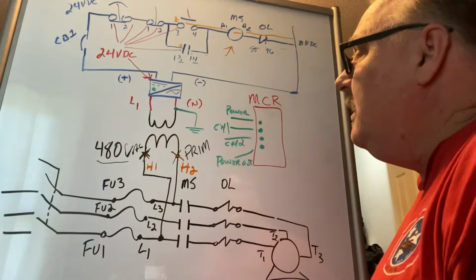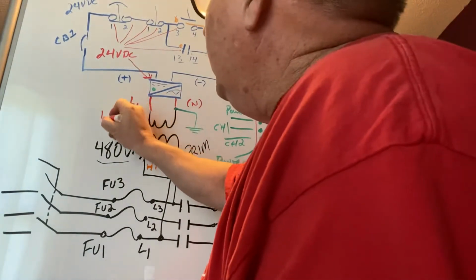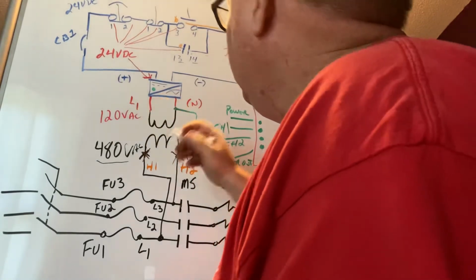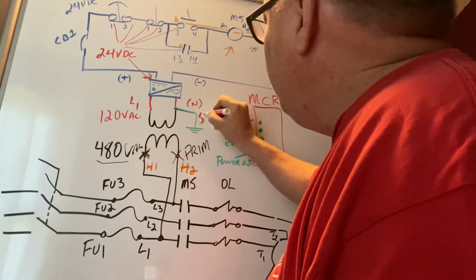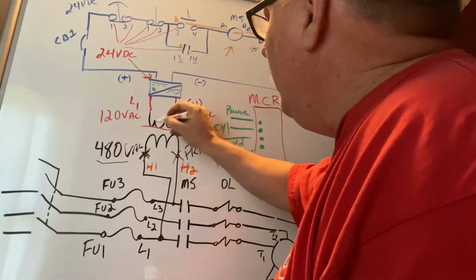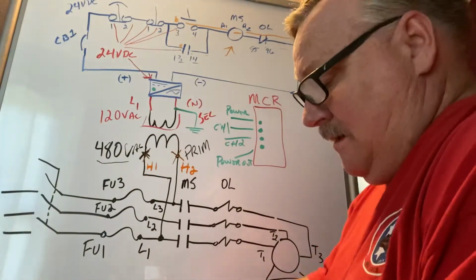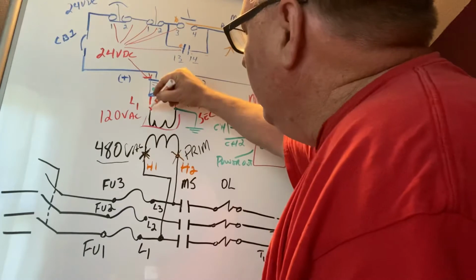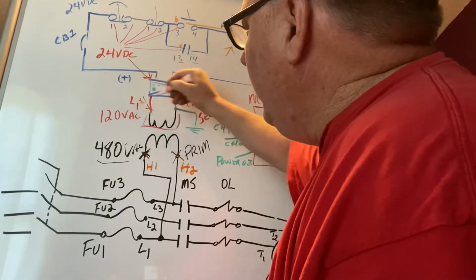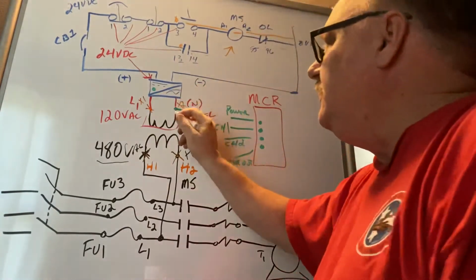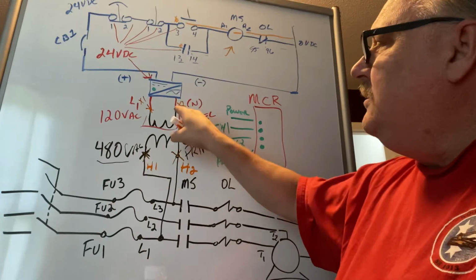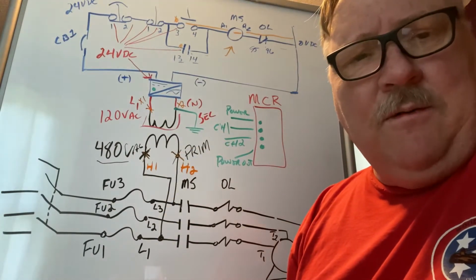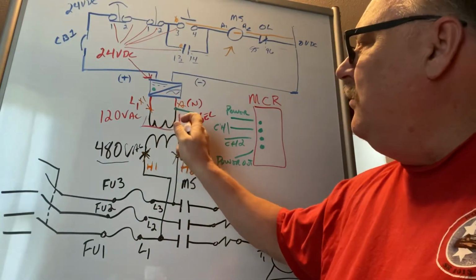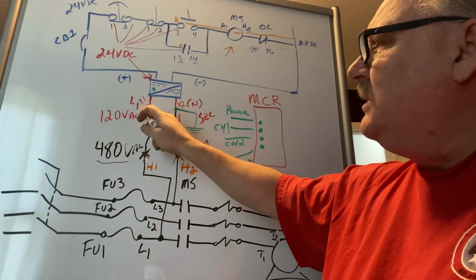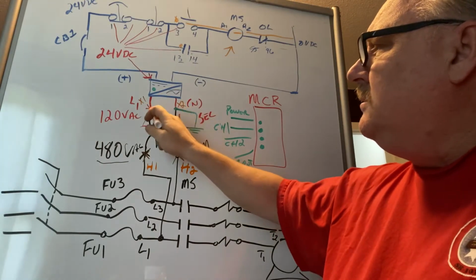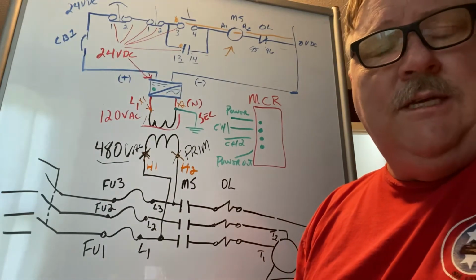The next one that you're going to see on your secondary side of your transformer is going to be 120 volts AC, okay? And this is on the secondary side, which is this part over here, okay? And you're going to have those voltages. You're going to have it from here, which is going to be X1 and X2. X2 is going to be your neutral. So if you check from ground to the neutral, you shouldn't get any power, you shouldn't see any voltage in that. When you go from ground to X1, or from your neutral to X1, you should see 120 volts AC, okay?